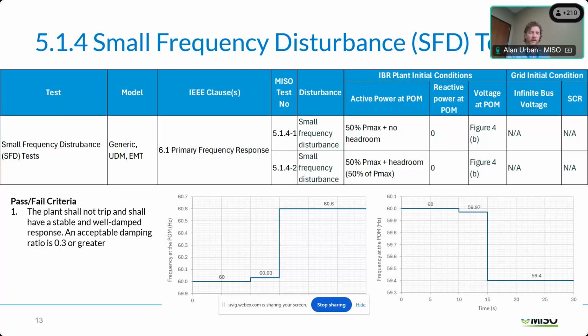So the idea is to kind of simulate if there's not as much sun shining or there's not as much wind, the resource is going to be limited to how much active power it can actually inject during these events. So we wouldn't expect to see, if there is no headroom, an increase in Pmax from 50%. And then, of course, we want to model the situation where you are just dispatched at 50% Pmax, but you have the availability to actually increase your active power, we want to be able to see that active power increase when needed.